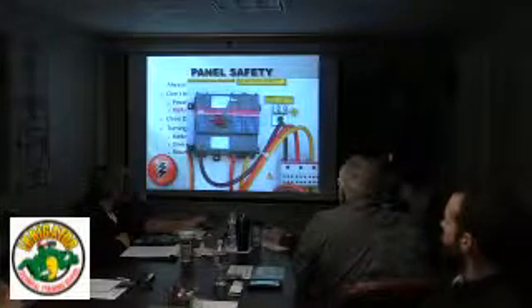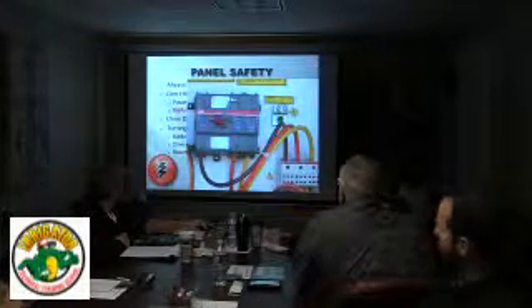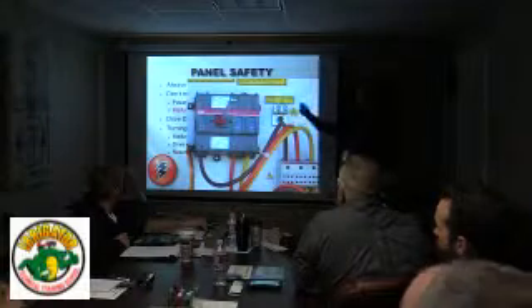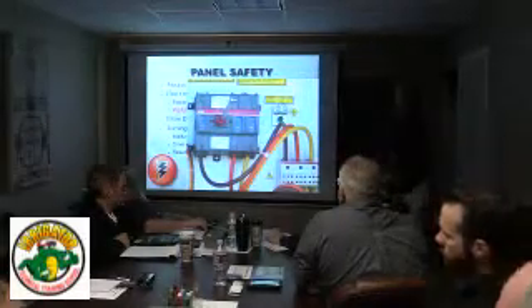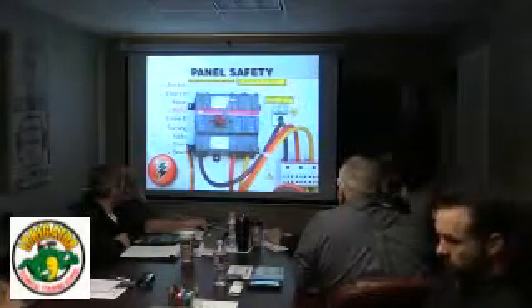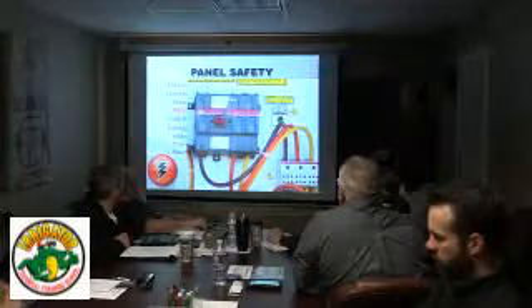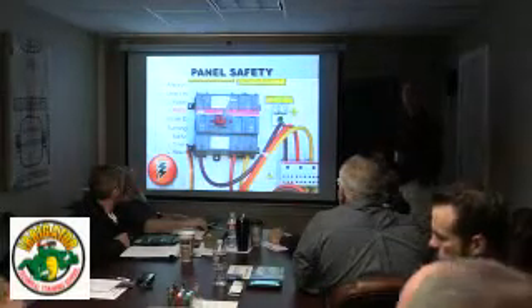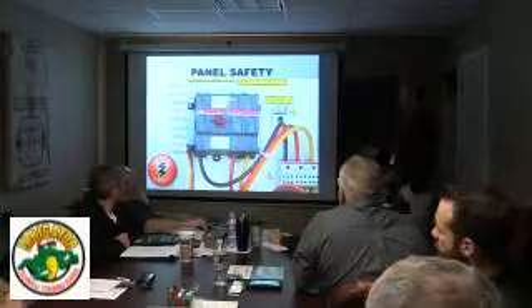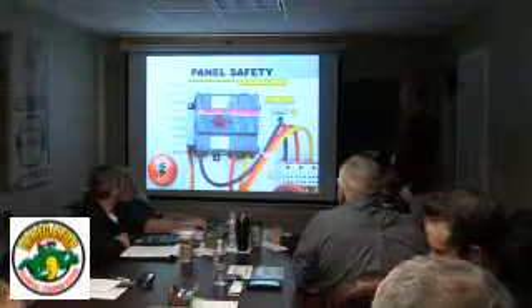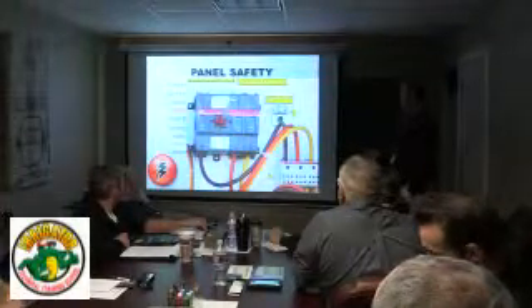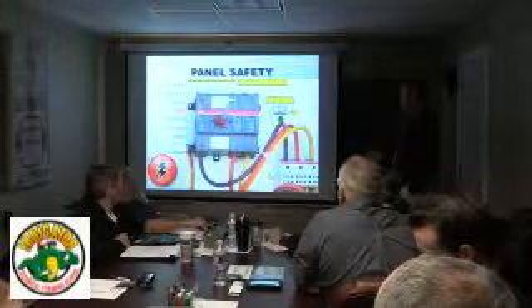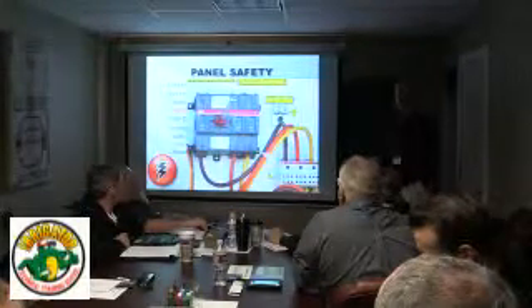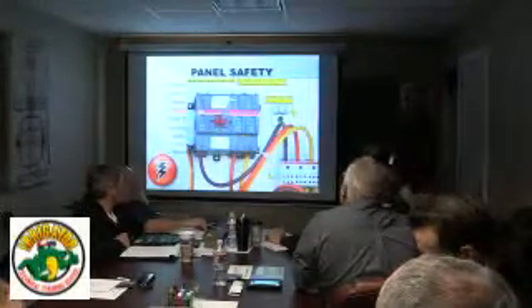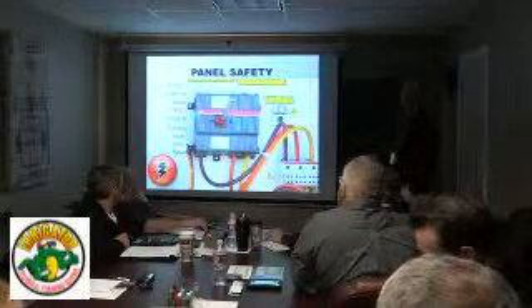Check your power. You might turn it off, and just because of a malfunctioning switch or other reasons, just double check and make sure that you measure across here. I always like to recommend too, if you measure power from phase to phase, like on this is a 480 volt system, you get 480 volts. Go through all 3 phases, but also what I like to recommend is go from each phase to ground.